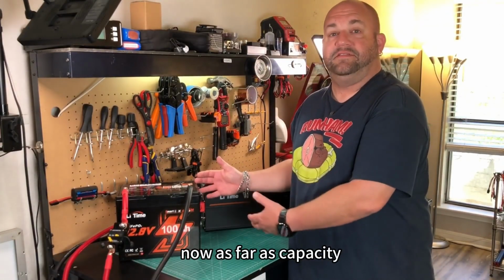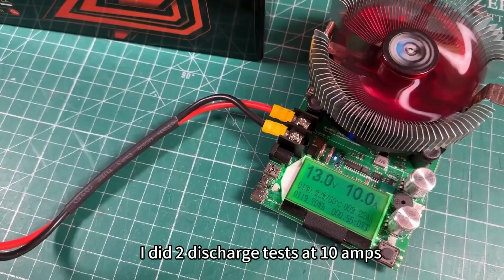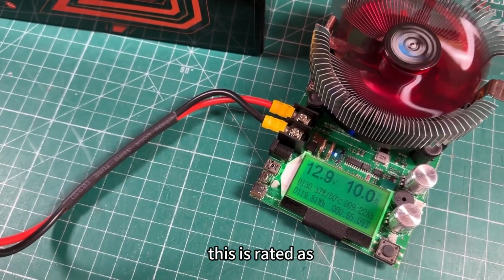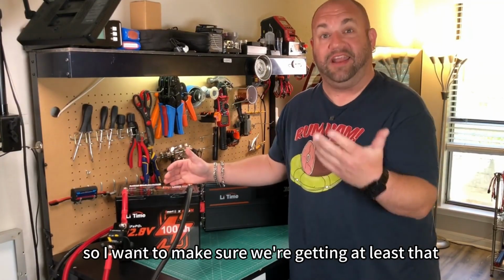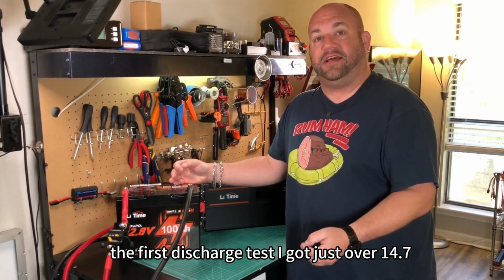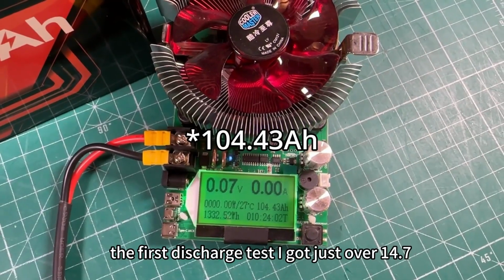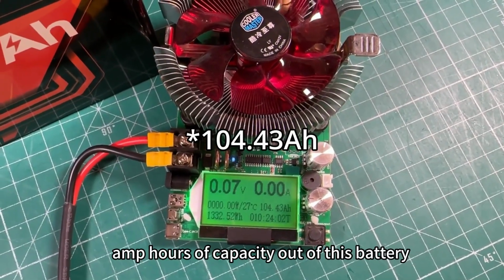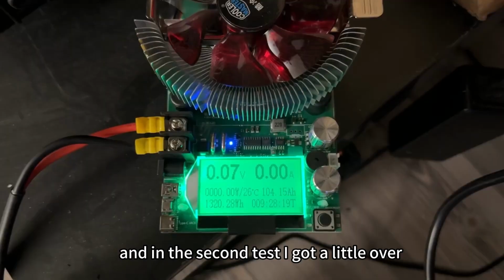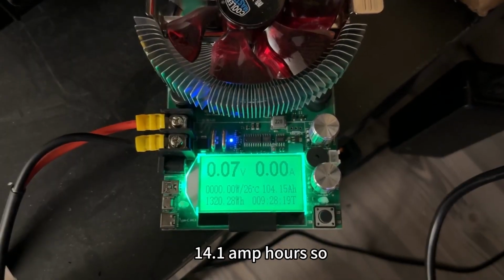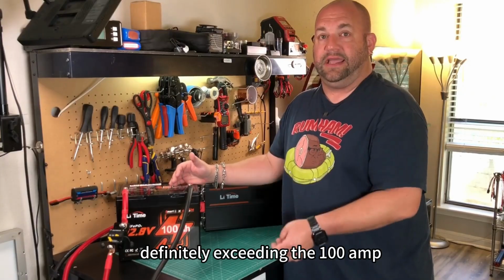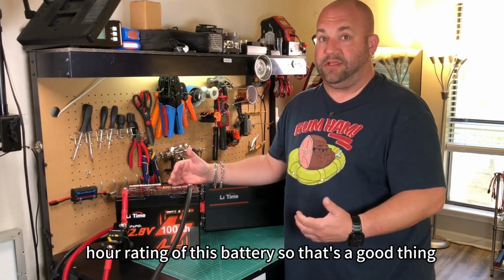As far as capacity, I did two discharge tests at 10 amps. This is rated as a 100 amp hour battery, so I want to make sure we're getting at least that. The first discharge test, I got just over 104.7 amp hours of capacity out of this battery, and in the second test I got a little over 104.1 amp hours. So it's definitely exceeding the 100 amp hour rating of this battery, which is a good thing.